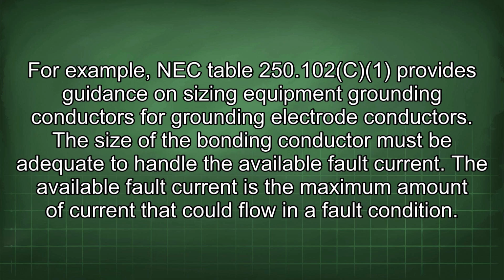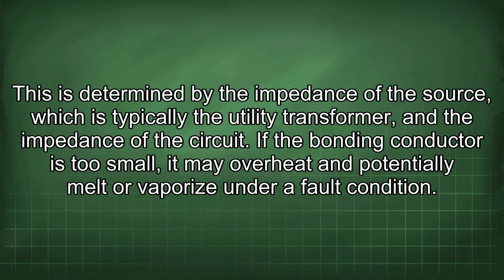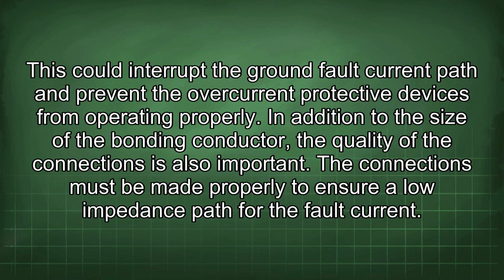The size of the bonding conductor must be adequate to handle the available fault current. The available fault current is the maximum amount of current that could flow in a fault condition. This is determined by the impedance of the source, which is typically the utility transformer, and the impedance of the circuit. If the bonding conductor is too small, it may overheat and potentially melt or vaporize under a fault condition. This could interrupt the ground fault current path and prevent the overcurrent protective devices from operating properly.